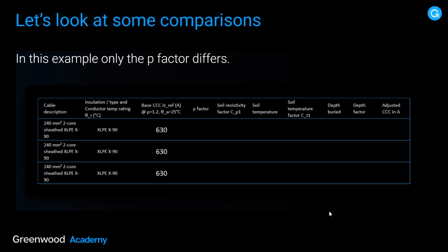This is the thing you have to get your head around. When it comes to current carrying capacity, it's all about heat dissipation, how quickly the cable can get rid of heat. When you're burying direct, in no particular order, how deep you go, the soil temperature, the thermal resistivity of that soil, and moisture and all those other things come into play as well. Now, in this example, only the thermal resistivity factor differs. Everything else stays the same. So we're looking at an engineered backfill of 0.7 thermal resistivity, and look at the adjusted carrying capacity in amps, 689 amps. And we're looking at depth of bury at 800 mil. Soil temp 25. The next example, we're going to 1.2, 556. We go to 2.5. This is truly horrible soil from a thermal resistivity perspective.